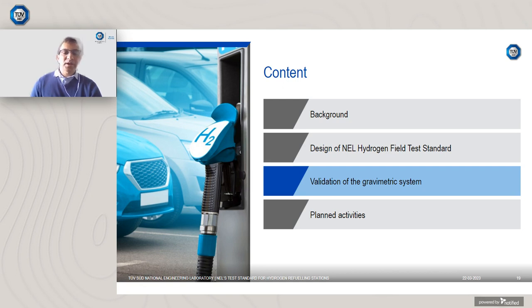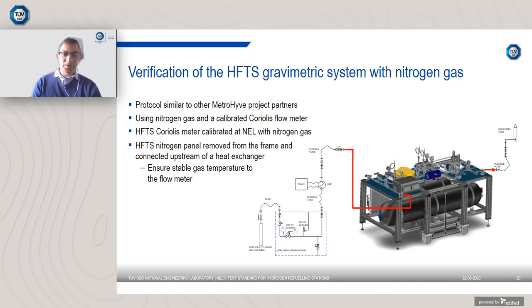Right, we shall now look at what validation tests we have conducted on the gravimetric system for the test rig. The validation that we carried out is similar to what the other measurement institutes had undertaken during the MetroHyVe projects. Essentially what we've done is to use a calibrated Coriolis flow meter and nitrogen gas to fill up the test rig to a known mass of nitrogen gas and compare what the test rig gives against what the Coriolis flow meter is telling us.